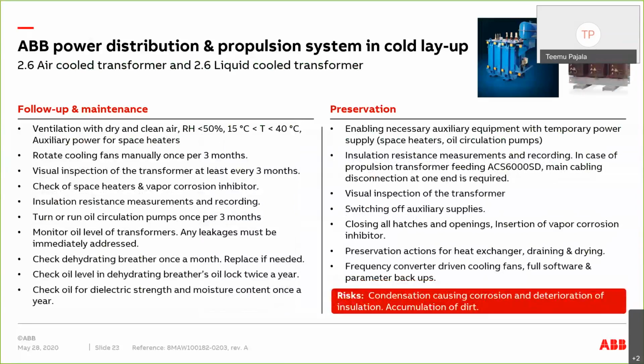Transformers. So for the transformers, all the powers can be switched off. They can be in cold state, but again, space heaters, the power for the space heater needs to be available, and power for ventilation fans and oil circulation pumps when they have been used. Otherwise, insulation resistance measurements need to be done and recorded. And then when the propulsion drive is ACS 6000 SD, remember that the main cablings need to be disconnected if you want to measure only the transformer.